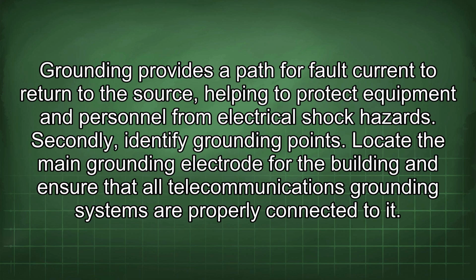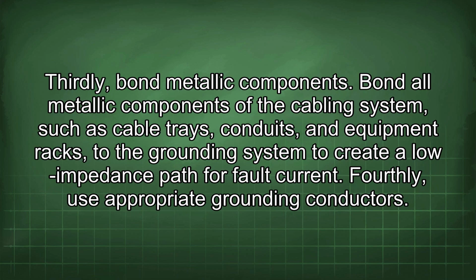Locate the main grounding electrode for the building and ensure that all telecommunications grounding systems are properly connected to it. Thirdly, bond metallic components. Bond all metallic components of the cabling system, such as cable trays, conduits, and equipment racks, to the grounding system to create a low impedance path for fault current.